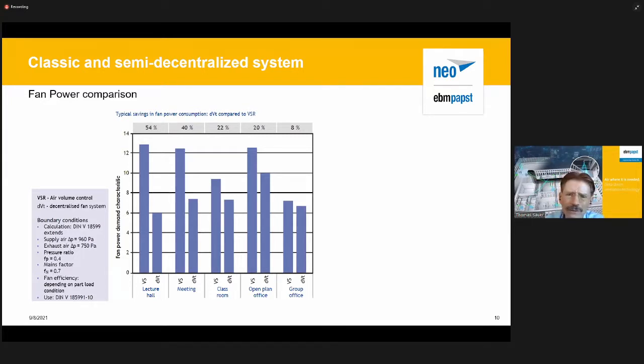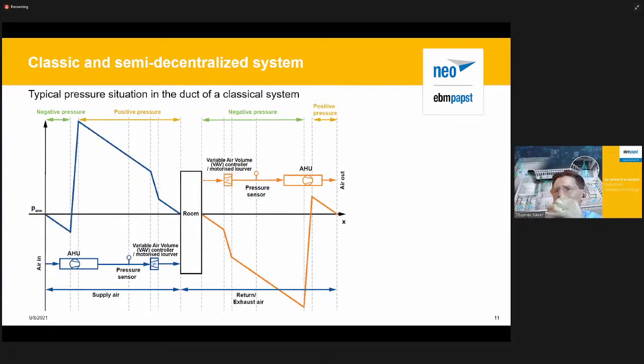Going a little bit more into the details of the technology is what we see on this slide here. That's the very typical way a system would look. We have the air handling unit, and what we see here, along the length of the airflow, is the pressure that we have in our air system. Before the fan we are sucking air, so we get a negative pressure, and the fan boosts the pressure to a high positive value, which is typically several hundred, maybe even more than 1,000 pascals. Then over the course of the channel the pressure drops. On the flap the pressure drops even more rapidly, and then the air is fed into the room. At the room, we should have around zero pressure to be able to open the doors.